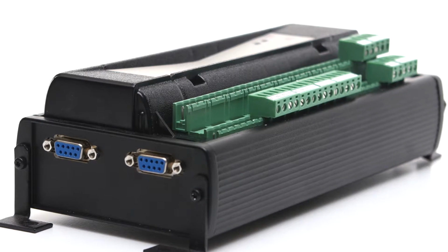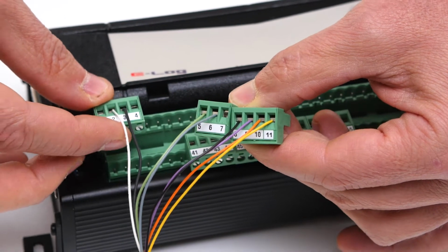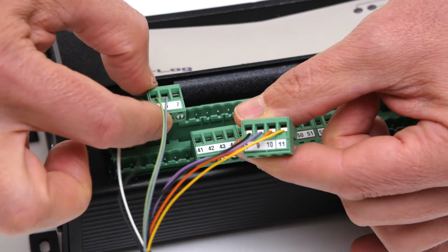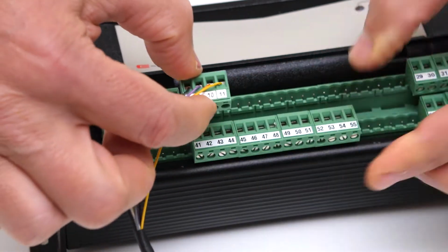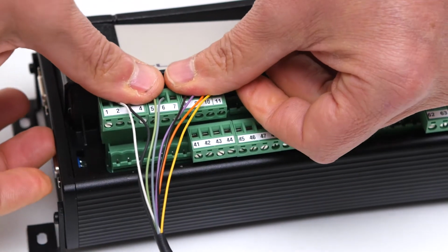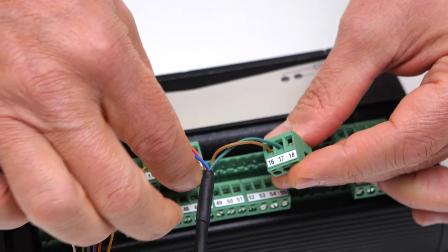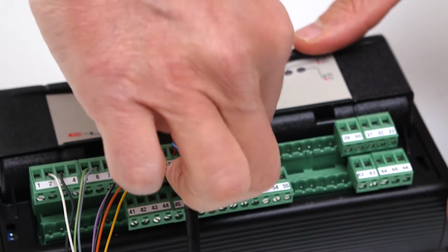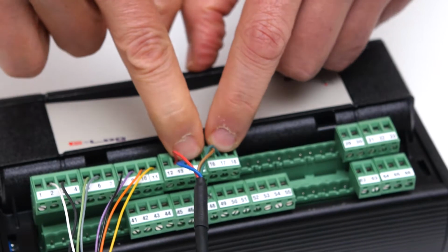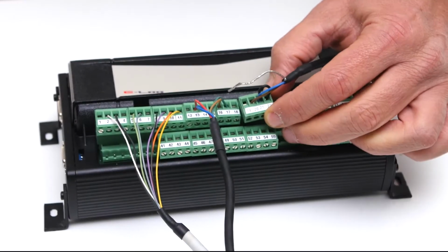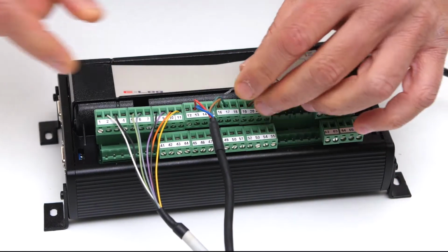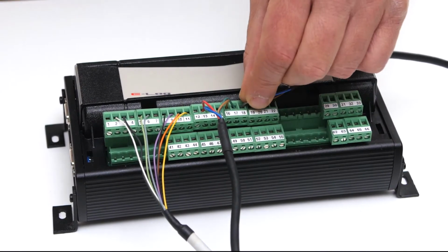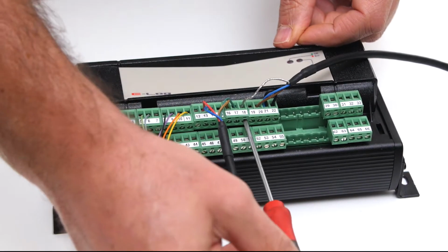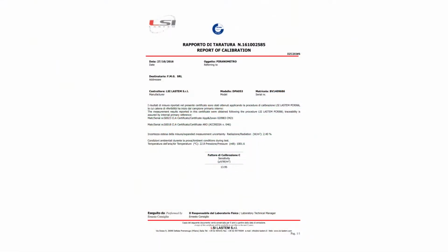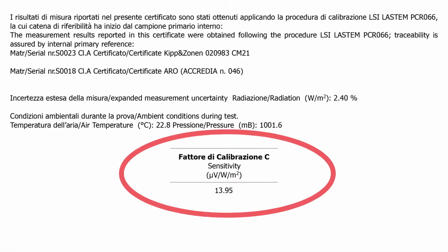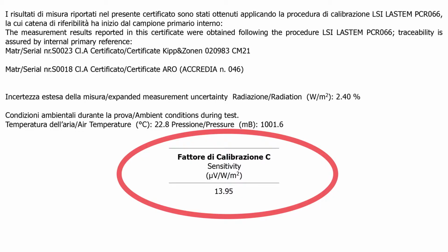Follow the numeric sequence. Insert the 3 connectors of the air temperature and relative humidity sensor. Check the good contact using a slightly deeper pressure. Insert the connector of the pressure sensor. Insert the connector of the radiation sensor and then screw the ground wire to terminal 18. Take note of the thermopile sensitivity value reported on the calibration certificate.